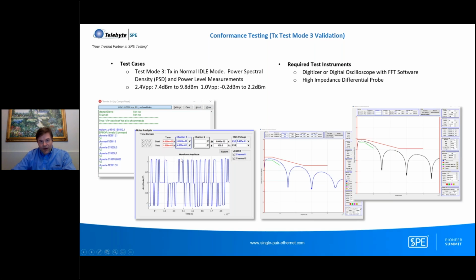But here, what we want to look at is a fast Fourier transform of the time domain signal, and we look at the frequency domain signal. Here's a signal in the 2.4 volt operating mode in blue, and we want to make sure that the power does not go above this upper red limit in a 2.4 volt mode, and then the green bar is the lower limit. So the transmitted signal must be between those two lines. Then we integrate the area under this curve to get the transmitted output power level.